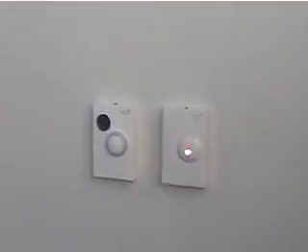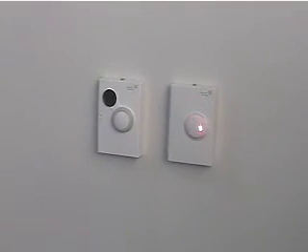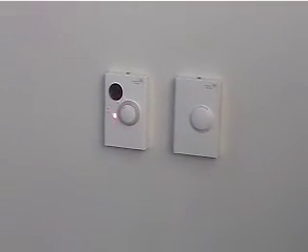A typical classroom, I believe it's level 3, room 314. Here we'll just real quickly talk about some of the VAV boxes and some of the sensors. If you look here on the wall, you see the sensor without any sort of display on it. That's going to be a CO2 sensor, and this right here is your zone sensor. The CO2 sensors are pretty much only in classrooms, wherever there are a lot of people, and they control the minimum ventilation of the room. We just want to maintain a minimum ventilation.